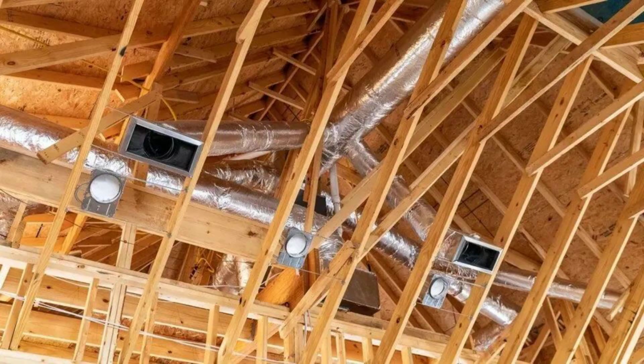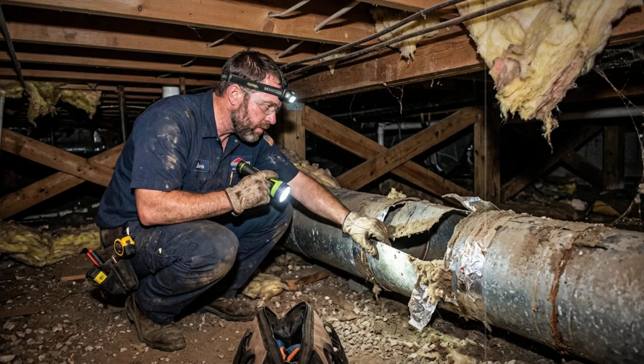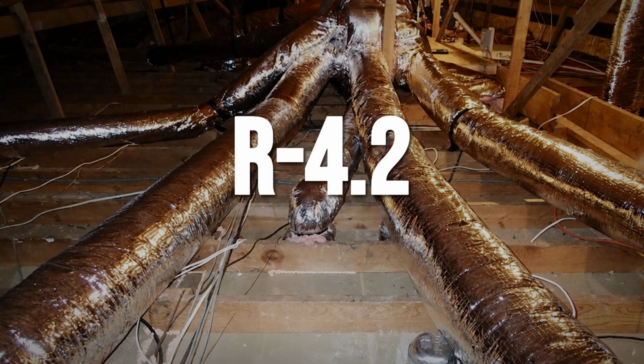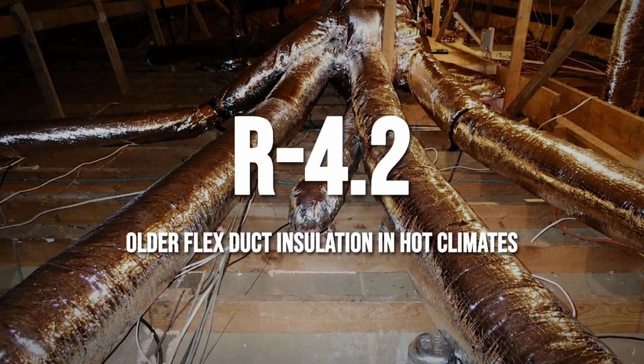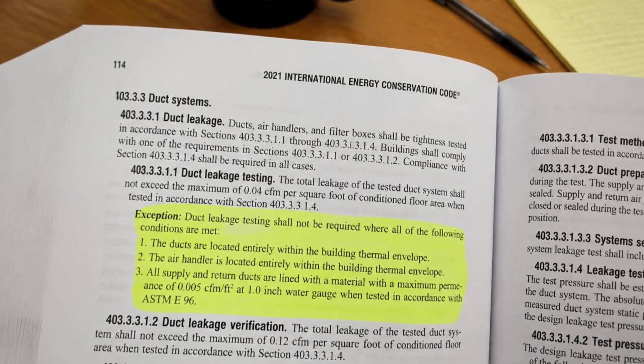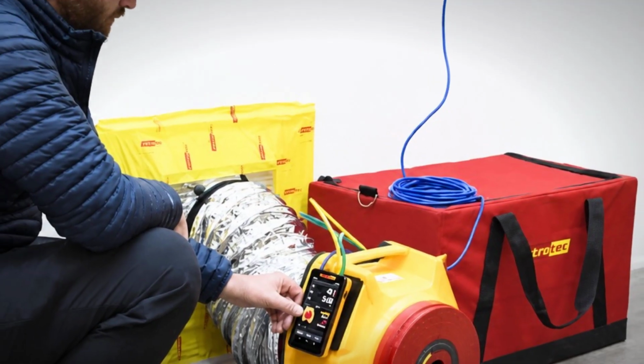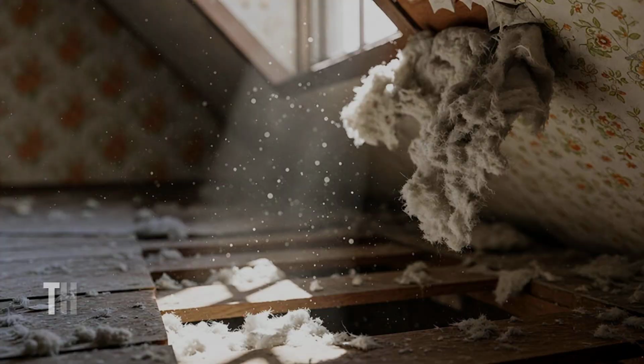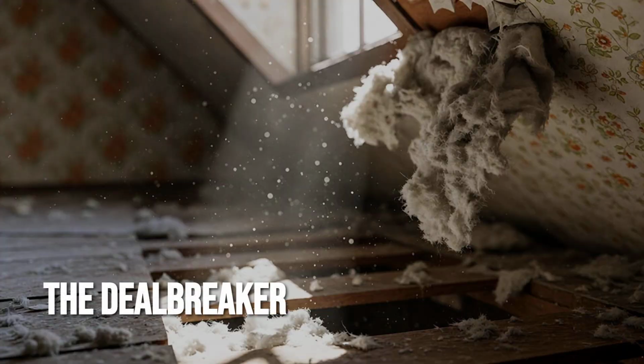Number 4. Already has ducts, is doing a lot of work. Every comparison I just gave you assumes existing ducts are usable. Plenty aren't. Older flexible duct in hot climates was often rated near R4.2. Current code in those zones calls for R8. And the 2021 Energy Code removed an exception that waived duct leakage testing. So more replacements trigger a test now. And here's the one that ends it.